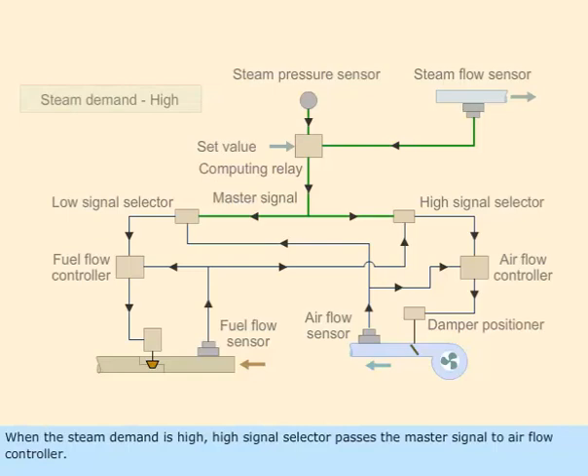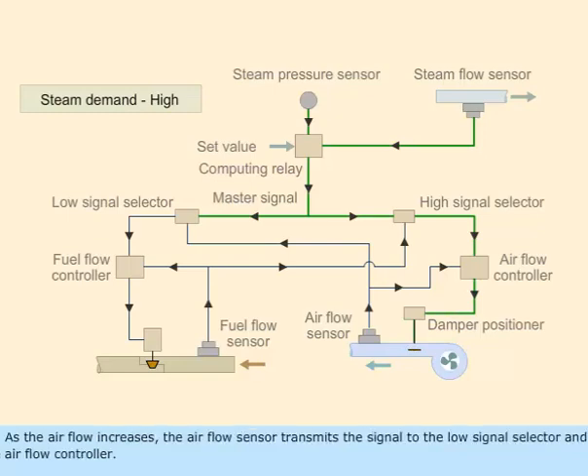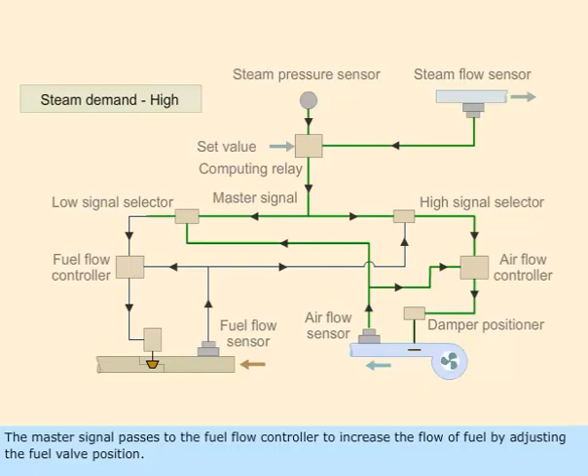When the steam demand is high, the high signal selector passes the master signal to the air flow controller. The air flow controller increases the air flow by adjusting the damper position. As the air flow increases, the air flow sensor transmits the signal to the low signal selector and air flow controller. The master signal then passes to the fuel flow controller to increase the flow of fuel by adjusting the fuel valve position.